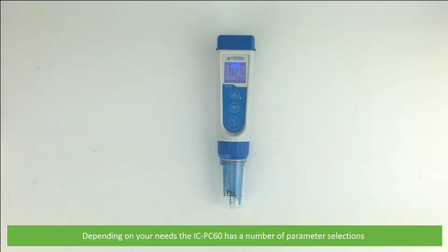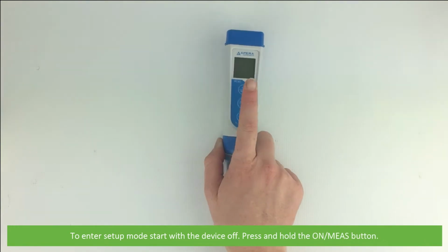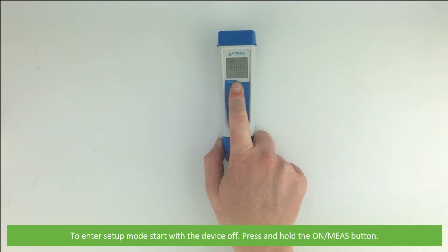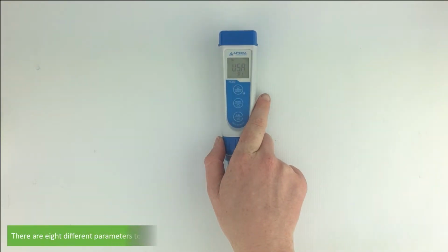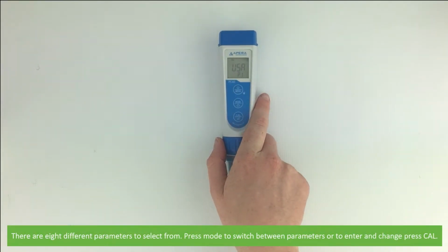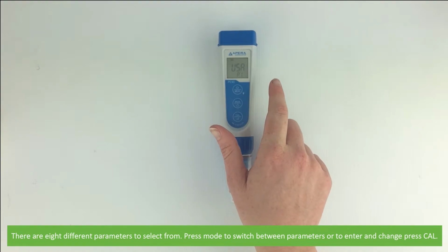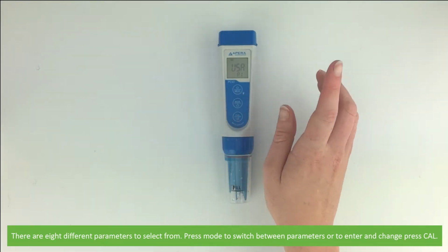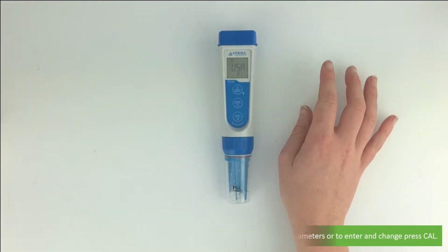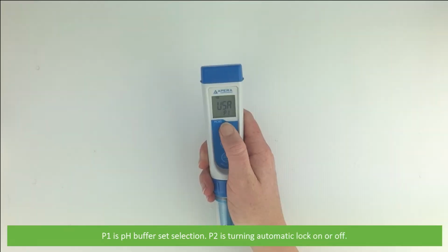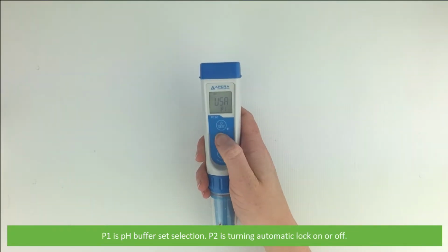Depending on your needs, IC-PC60 has a number of parameter selections. To enter setup mode, start with the device off. Press and hold the on/measurement button. There are 8 different parameters to select from. Press mode to switch between parameters, or to enter and change, press cal. P1 is buffer set selection. P2 is turning automatic lock on or off.